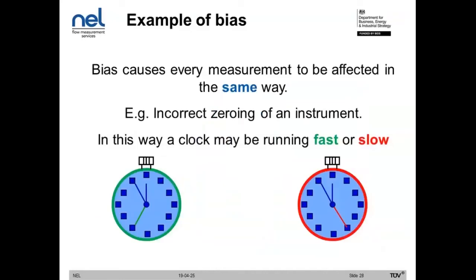Another obvious example of bias is if you have a watch and you set the time and the reference that you use to set the time on your watch is incorrect. So let's say it's out by a minute, and your watch is then reading 1 minute fast for the rest of the day, or the rest of the week, or until you calibrate it again. So whatever changes happen to the watch itself, there's always going to be that offset additional to those effects. So you have a systematic error that can't be removed without recalibrating.